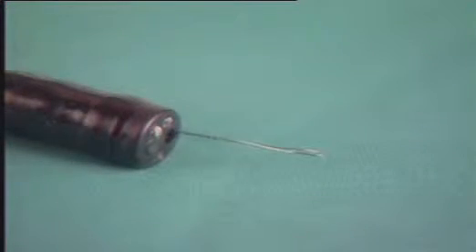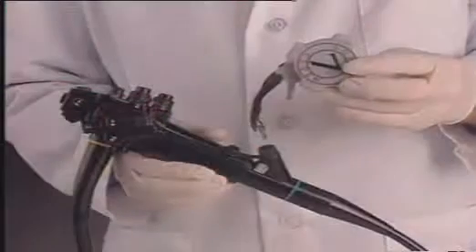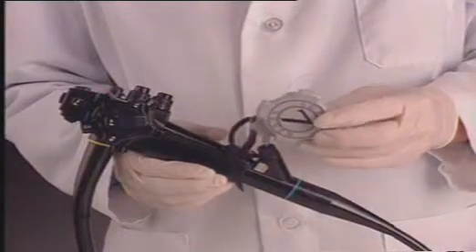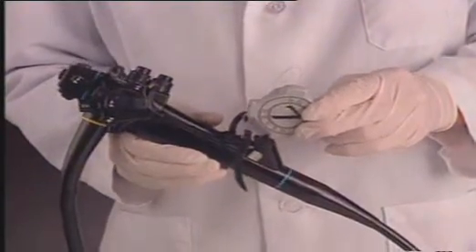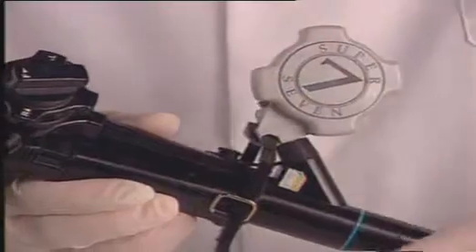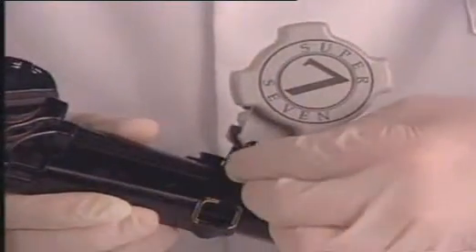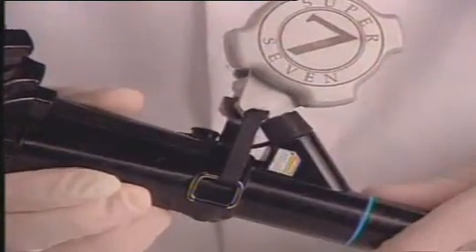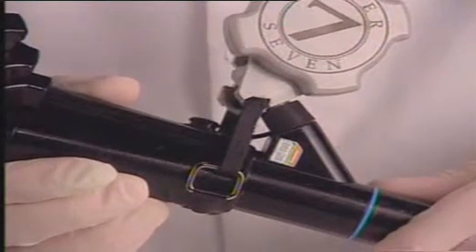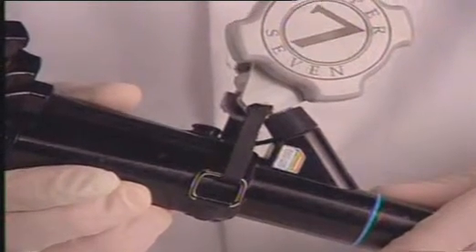Begin assembly by inserting the distal end of the tripwire through the biopsy valve, and then the working channel of the endoscope. Continue feeding the tripwire until the wire loop exits the distal end of the endoscope. Then, firmly install the stem of the handle unit onto the biopsy valve. Install the handle unit into the biopsy opening of the endoscope by wrapping the scope fastener around the endoscope and locking it into place.